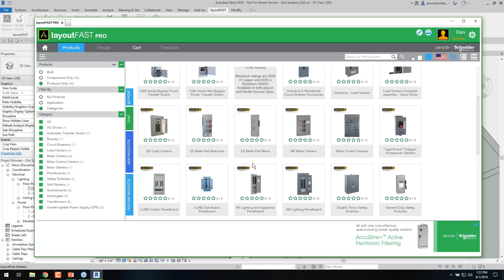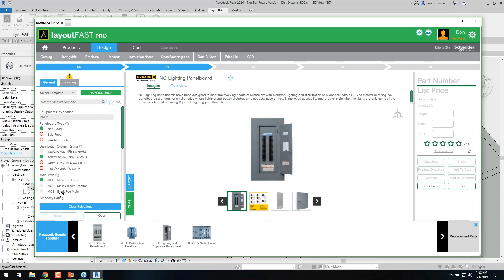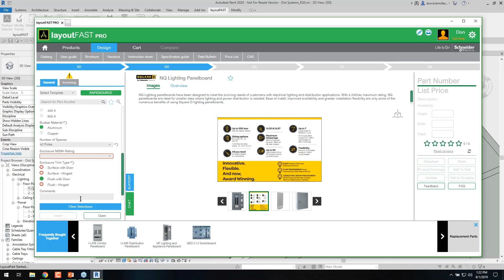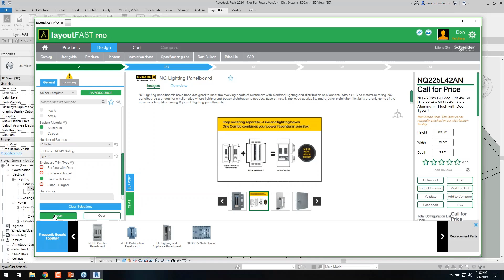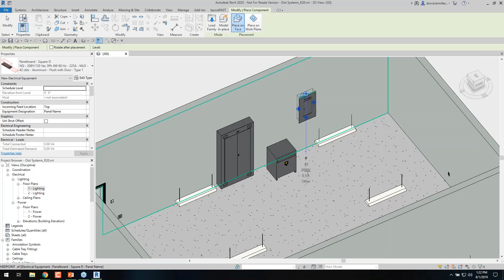In this case, I'll go with an NQ panel, a lighting panel board or branch panel board, whatever you want to call it. It's going to be panel A. Let's say this is a 208 main lug, right there. Maybe I need a 225 amp panel with aluminum bus. I want to do 42 poles, and I want this to be flush mounted in a type 1 enclosure. So again, I fill out my criteria, I get my actual product, I click insert, and place it into the model.